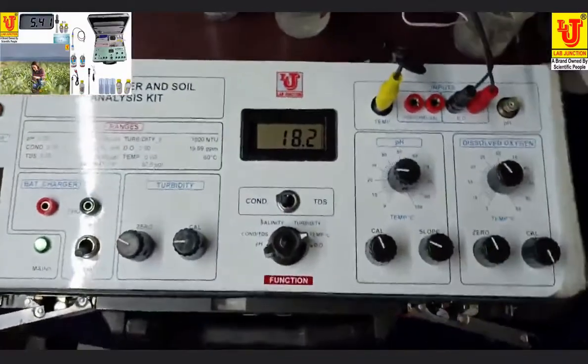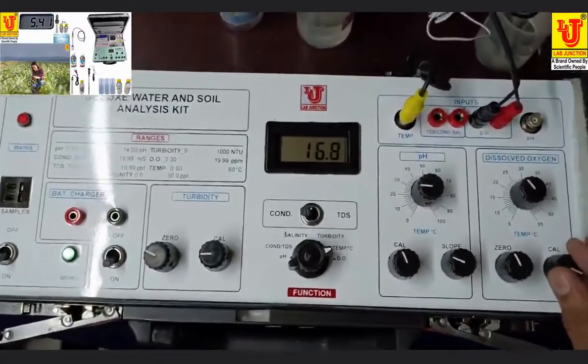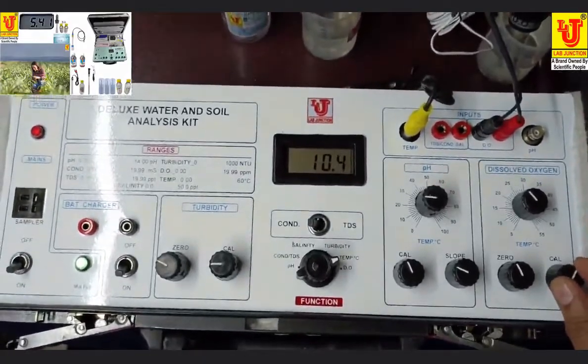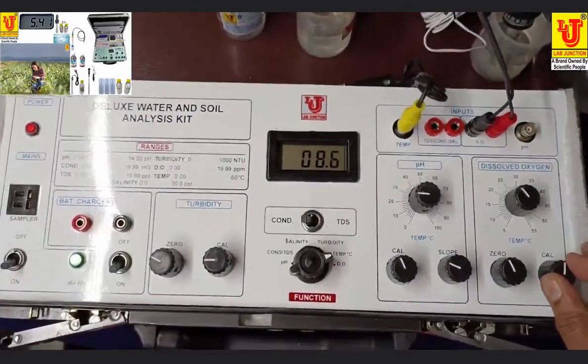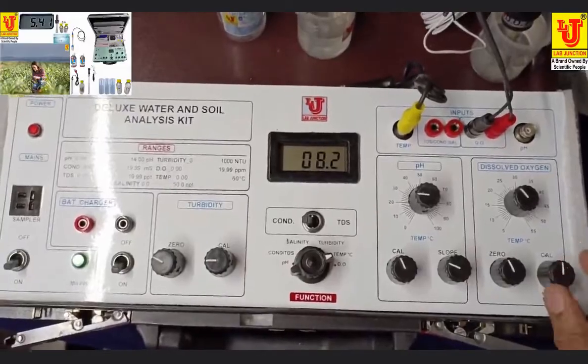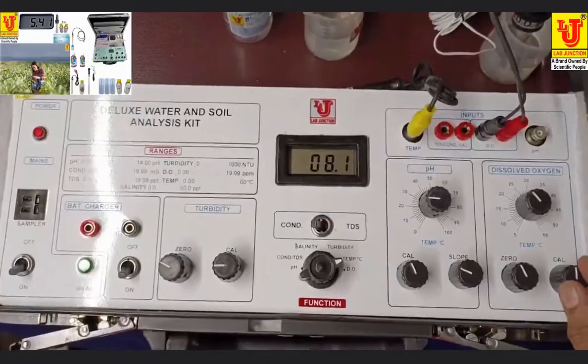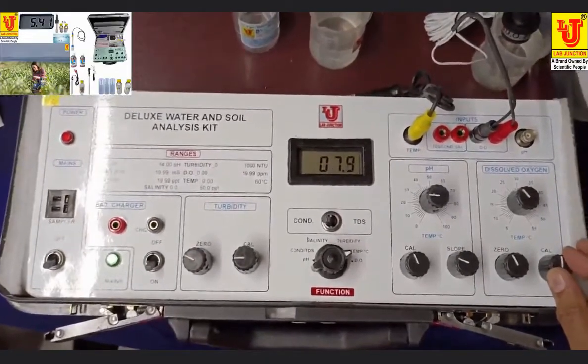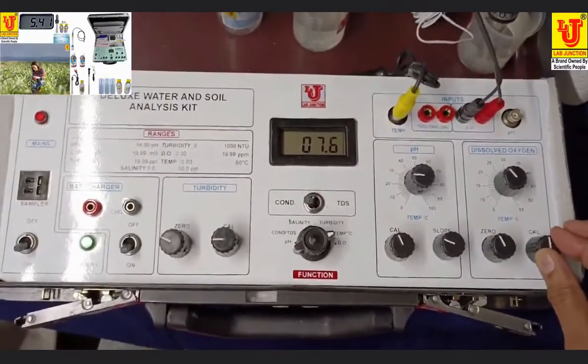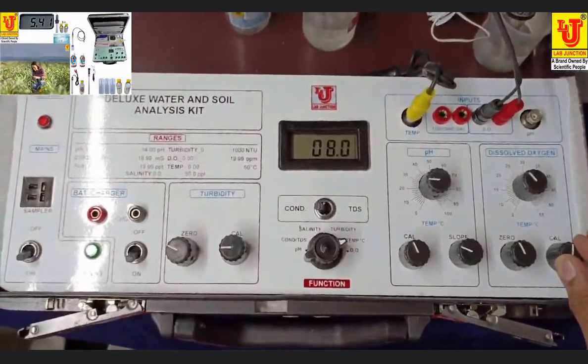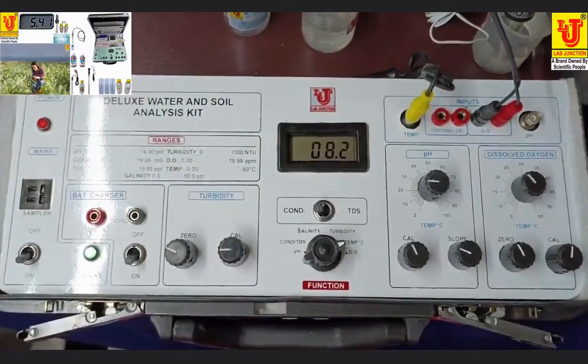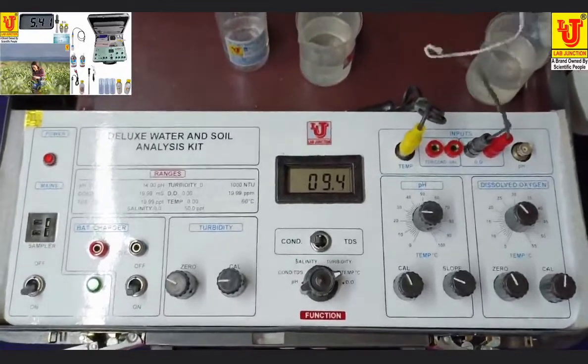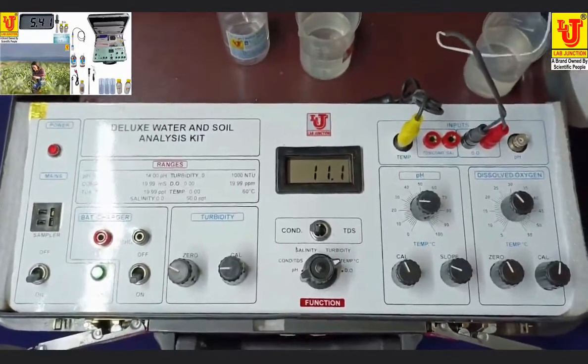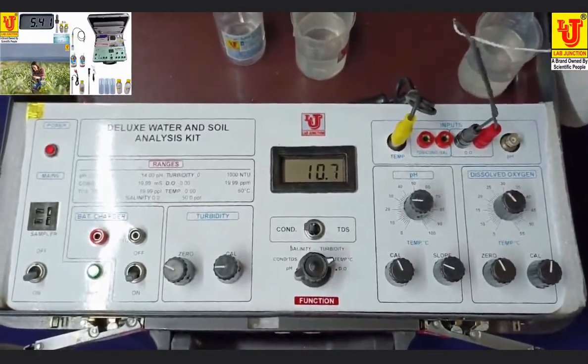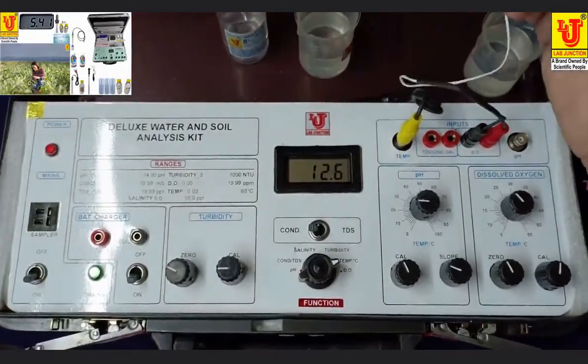For any other temperature value, see this table. 25, 8.2. You can feed the value from the cal control, like this. Now your dissolved oxygen parameter with chemical method is ready for use. Now your dissolved oxygen probe sensor is okay.